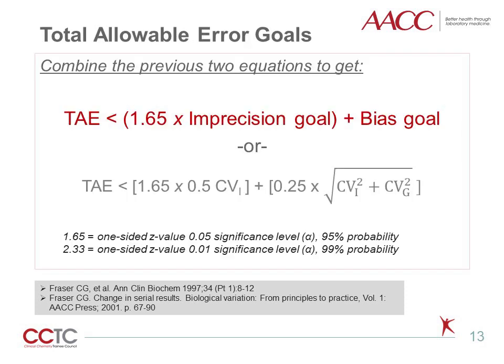Total allowable error, TAE, is derived by combining the two previous equations. The standard calculation for TAE is 1.65 times imprecision plus bias, where 1.65 is the one-sided 95% significance level based on a Z-distribution. If setting TAE limits to 99% probability, 2.33 is used as the multiplying factor instead of 1.65.